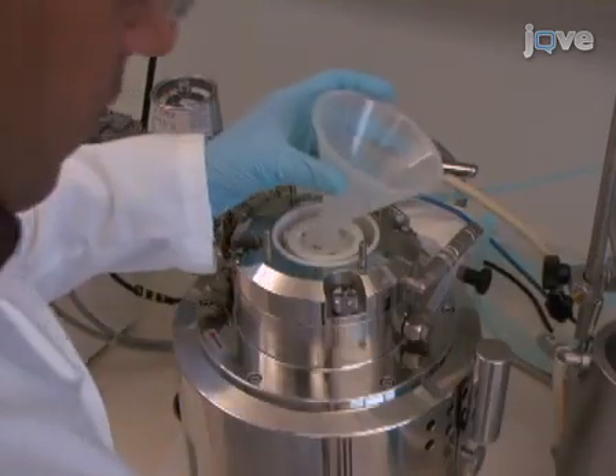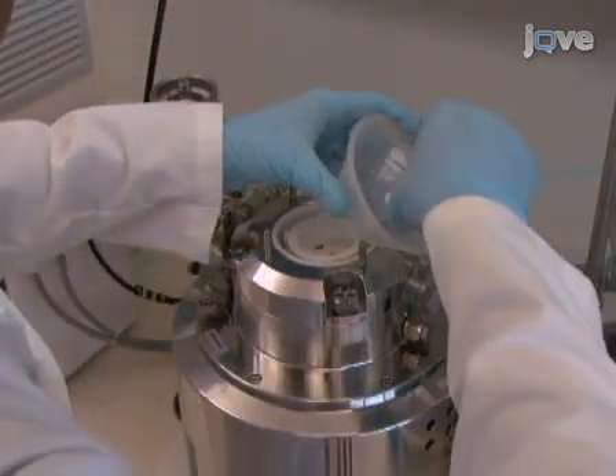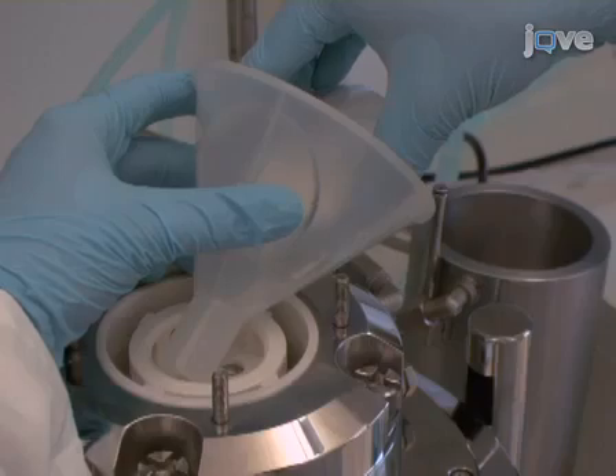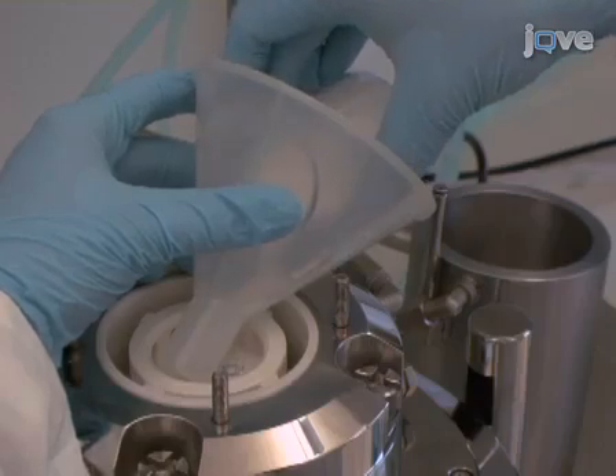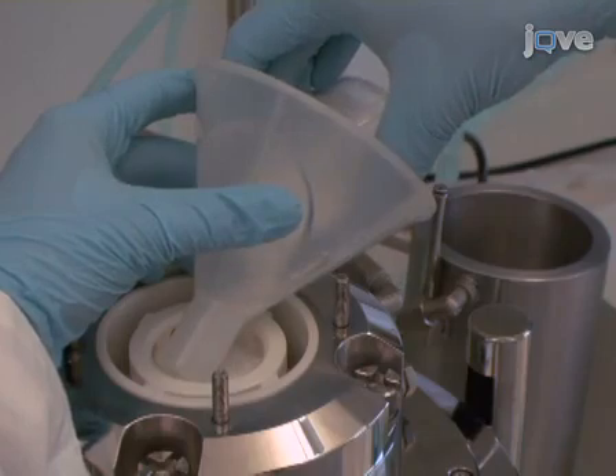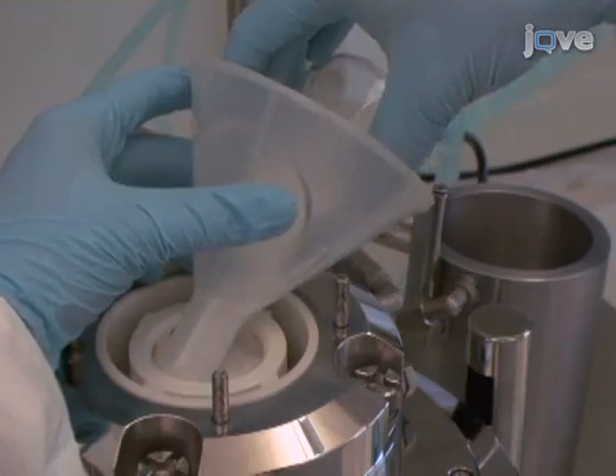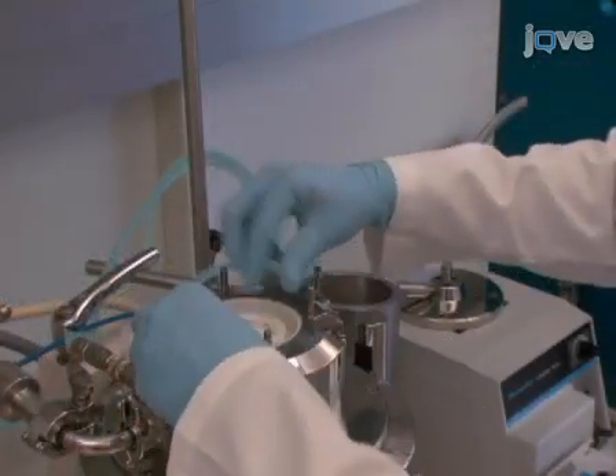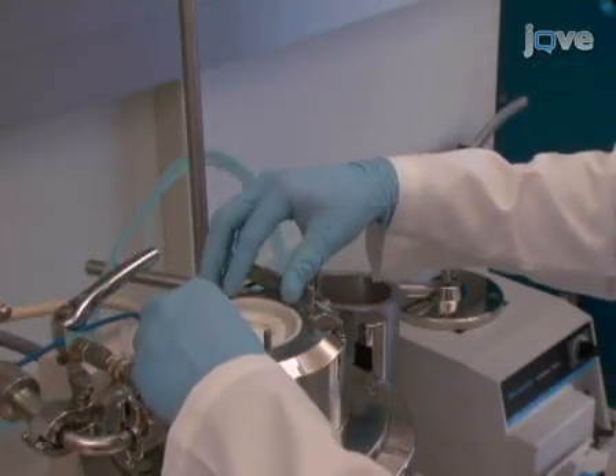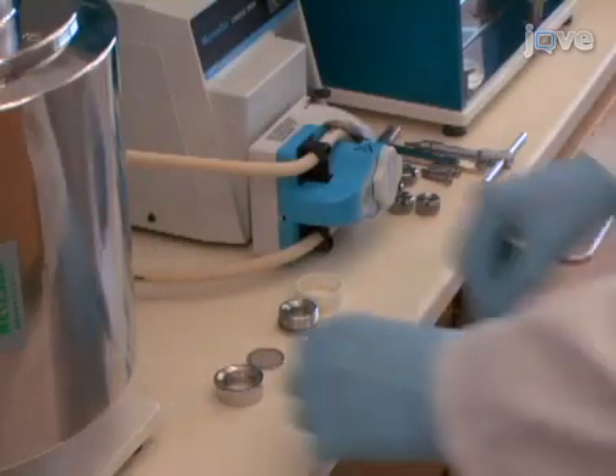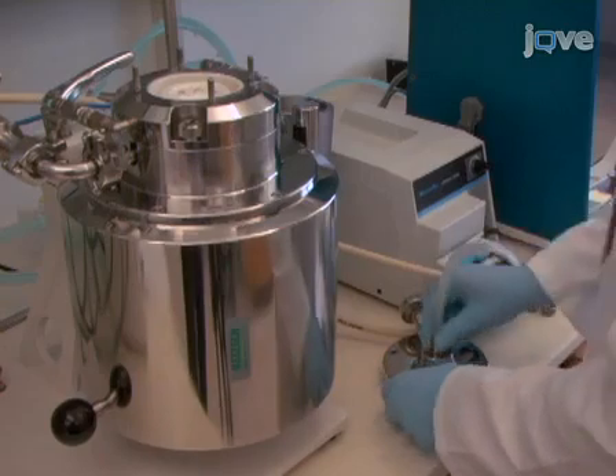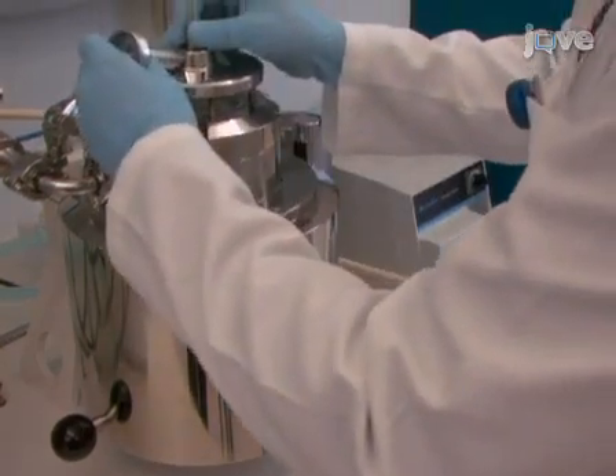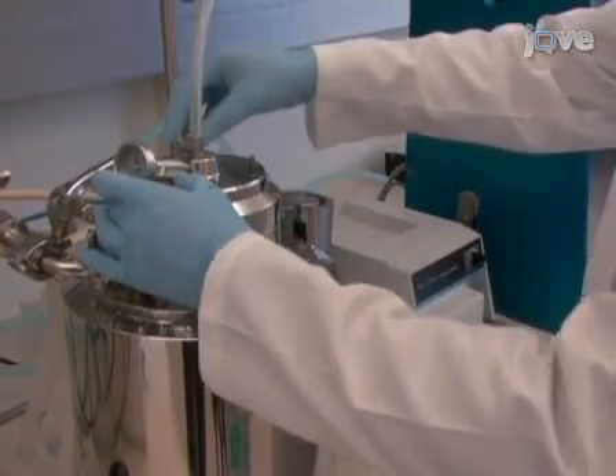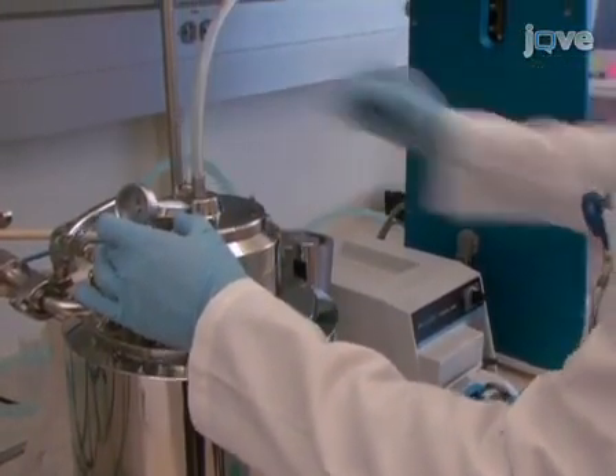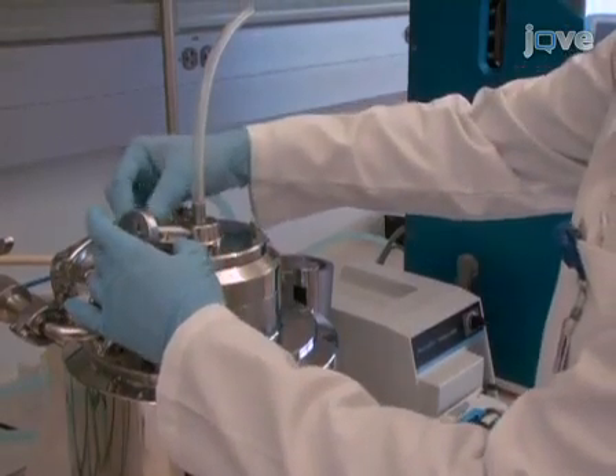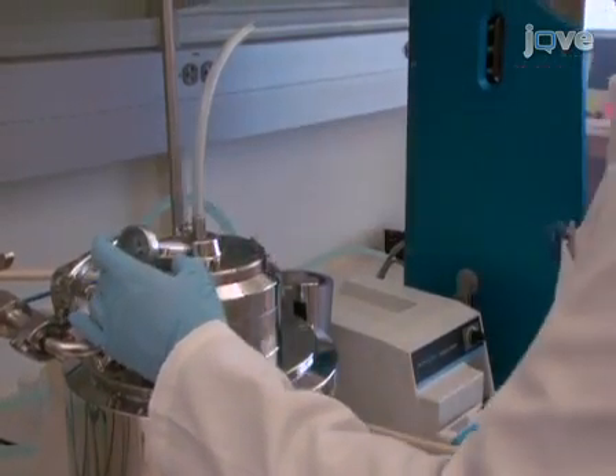And add 50 milliliters of beads to the grinding chamber using a funnel. Make sure that there are no beads in the threads or anywhere outside the grinding chamber to avoid leaks in the mechanical seal. Now make sure that the O-ring is in its place on the milling chamber. Then, select an appropriate screen mesh size and secure the lids by tightening the nuts. The screen mesh size should be at least half the size of the beads. Use a large screen mesh size to avoid the product from clogging the filter while continuous milling.